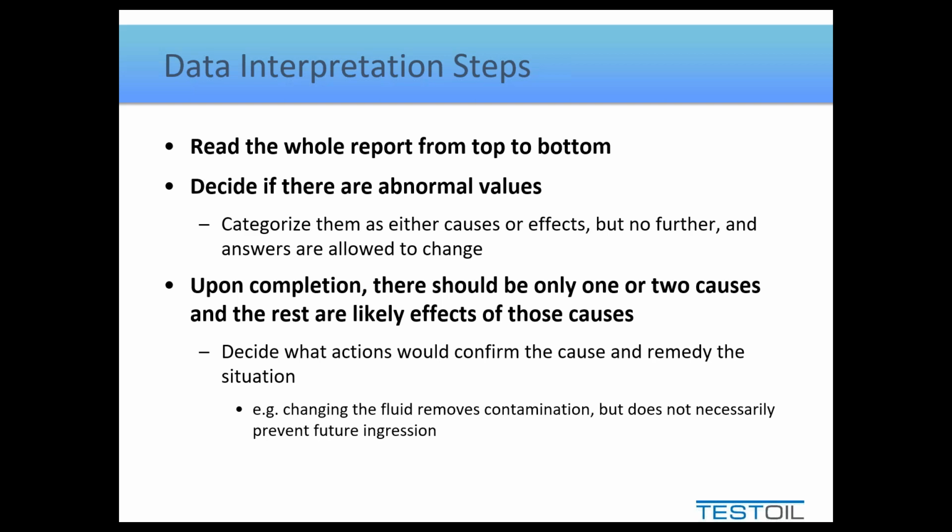I always kind of take pause there, because I'm like, well, yes, I understand where you are. The results are high. You don't like them. Changing the oil would certainly reduce them. It doesn't fix anything though. Right? We need to know what will fix something. So we may still in the end decide the oil has to be changed because we can't live with it, but understand that simply changing the oil just makes for a better report, doesn't make for a better machine. The example we're going to go through today, that won't be relevant, but I like to point it out every time I can. So we're going to go through an example now, and here's the example.